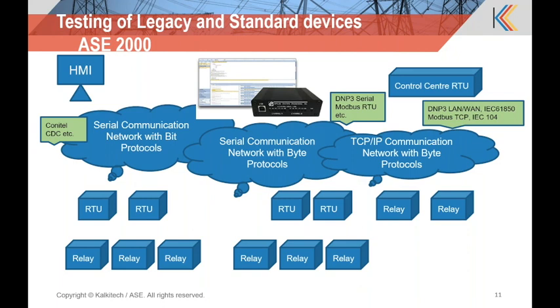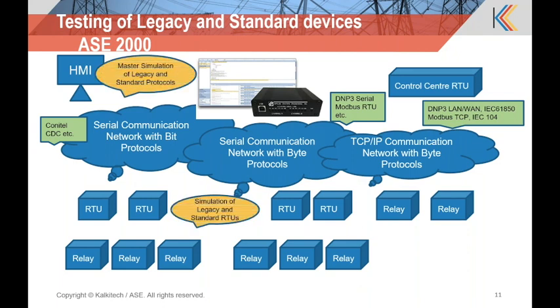Master simulation, RTU simulation, and monitoring. When it comes to monitoring, there's a couple of different means. You can monitor live, passively, serial communications, or via an IP mirrored port, you can actually capture live two-way Ethernet traffic between your control center, master station, and RTU.